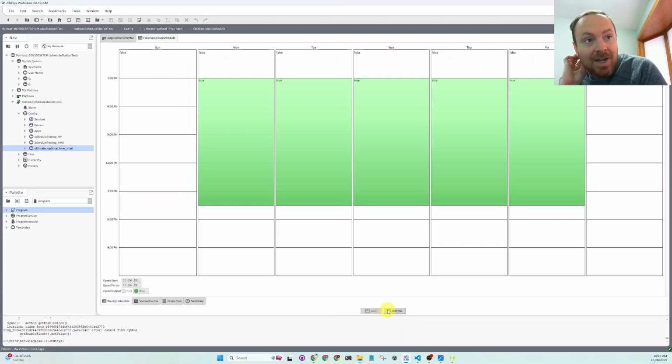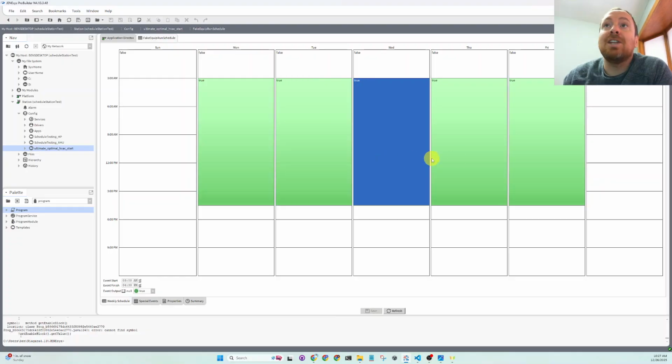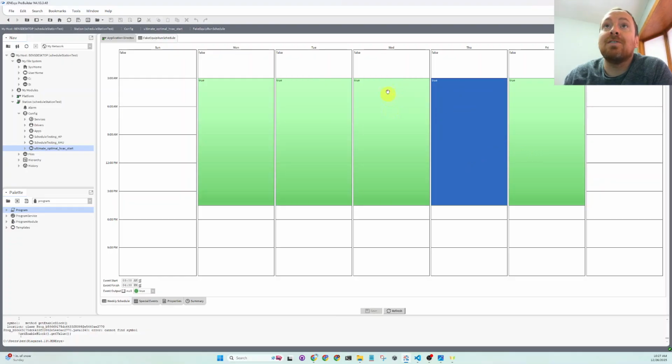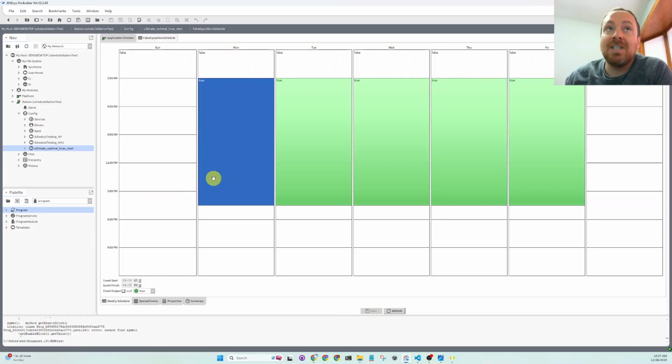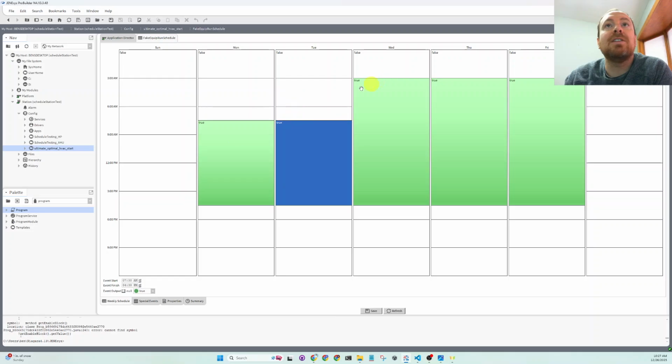They get graded on how many temperature complaints they have. So if I run HVAC really long, it burns a ton of wasted fuel. They don't pay the utility bills. They don't even see it, so that's why they do it. So we're working on these optimal start algorithms where people come into the building, let's say here and here, and we're calculating that optimized time delta so they don't have to do that.